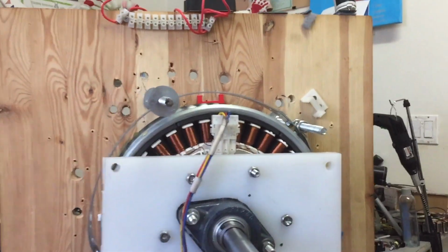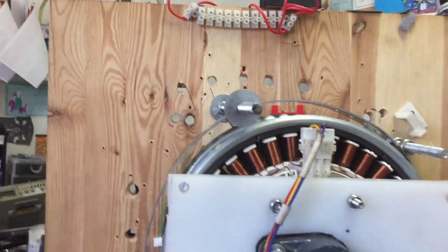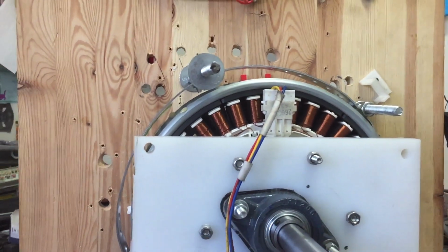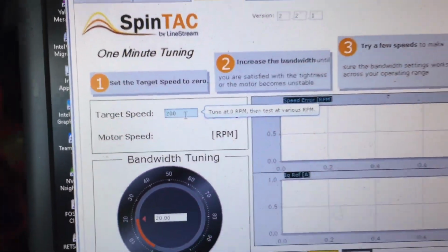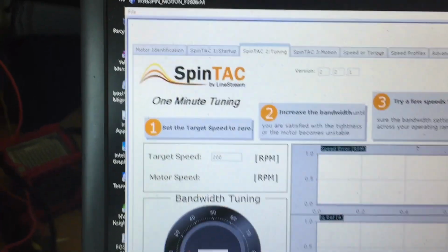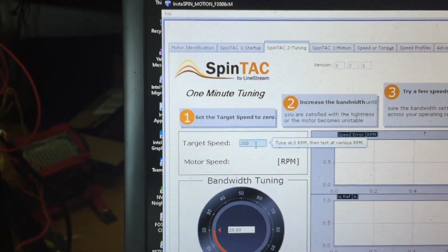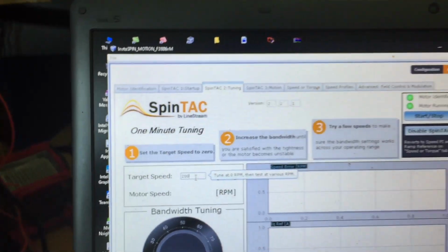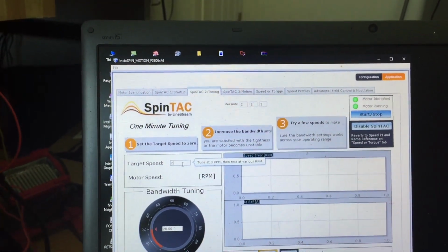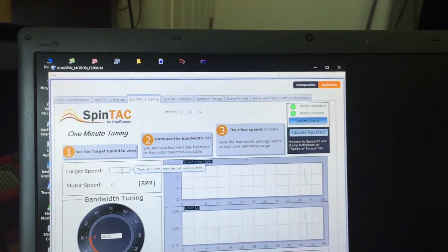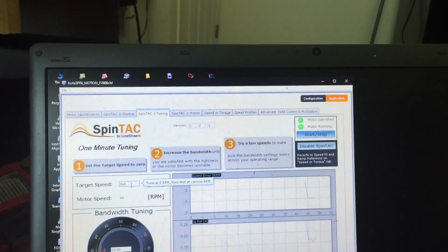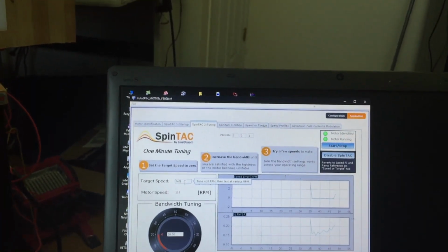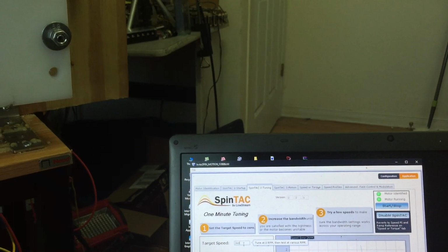Now we're going to take off these coils and try the same test again. Okay guys, so now I removed all the coils. Now there are no cores around it. We're going to do the same test at the same three speeds that we tested before: 360, 485 and 600, and check the input power required by the motor, the prime mover.